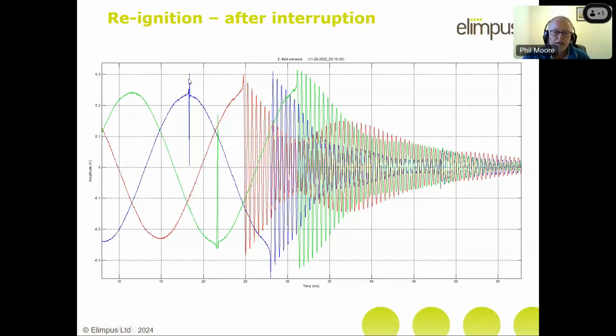I've chosen this because it's a particularly bad one, but you can see here there's a very large reignition at the peak of the blue phase voltage, and there's also a very large one at the peak of the yellow phase voltage. Incidentally, I'm saying yellow phase, but I use green on a white background, so it just sticks out better. So where you see green, I'm talking about the yellow phase. For this particular breaker, that wasn't particularly an issue because they knew that the breaker was randomly switched. They were expecting to see this.